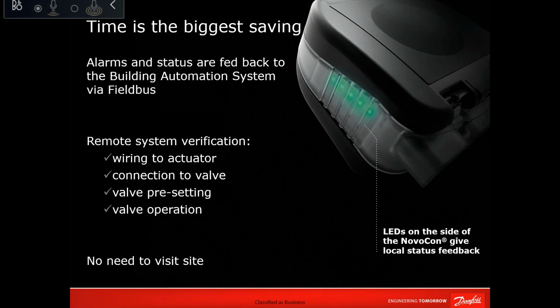Even the model of the ABQM used with the Novocon M and L will have a different neck because there will be a spring, and also there will be no scale to set the flow, and there will be a different override of the flow setting mechanism, which we are keeping only as a safety feature. So yes, from the Novocon you set it, and you don't need to set any single valve.